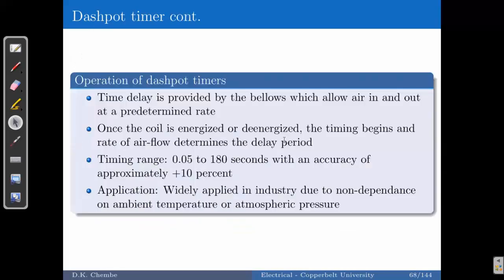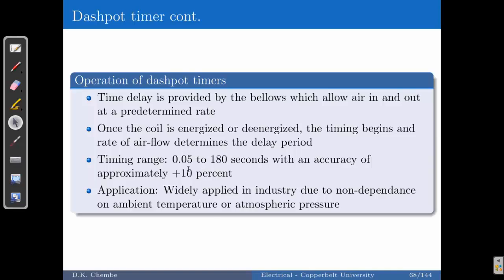The time delay for dashpot timers is provided by the air bellows, which allow air in and out. Once the coil is energized or de-energized, the timing begins, which allows the air to flow in or out at a delayed period. The timing range can be from about 0.05 to about 180 seconds, and the accuracy is about plus or minus 10%, which is relatively good.